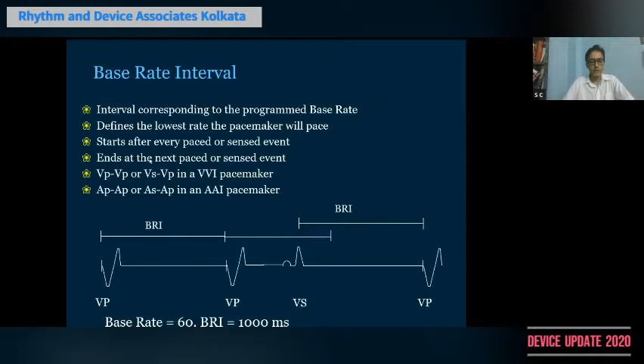Again, VVI timing. If there is ventricular pacing, the time from one ventricular pace to the next ventricular pace is the basic rate interval. If there is a sensed event like the third one, the base rate is interrupted. Some pacemakers, if you interrogate them, give ladder diagrams which show this basic rate interval. In the third one, you can see that the basic rate interval is interrupted by a sensed event, and a new inclined slope starts, which indicates the new base rate interval.